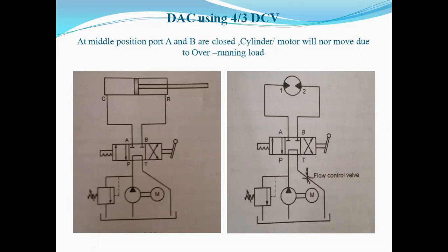in a sudden manner. If we consider that the motor is running at 40 RPM in the clockwise direction in the forward case, and when we change the supply suddenly in the return direction, in a fraction of a second we are changing the oil passing through this return line. Your return line will become the pressure line in that case, and due to inertia, this motor will start rotating at, let's consider, 440 RPM.